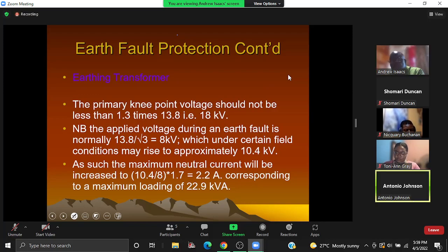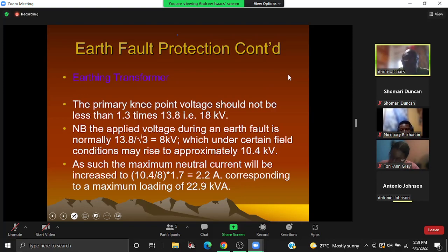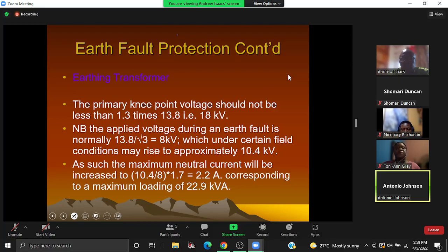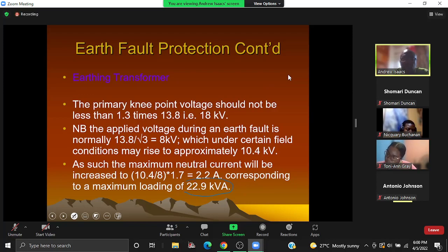Sorry, you can go back to that last line. I get that. You can hear me? Yeah, man. So we have the 1.3 ratio being multiplied by the 1.7, to get the 2.2. And what I'm not getting is the maximum load in here. Yes, this is not a rating on the loading on the transformer.